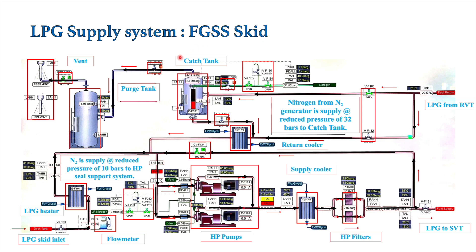Next, let's see why we have a catch tank in the FGSS skid. The catch tank comes into use when we are either starting or stopping the engine. During starting, this catch tank provides positive suction head to the HP pumps. The catch tank is always maintained at 23 bar, and this 23 bar pressure is maintained by nitrogen supply. Nitrogen is supplied at around 34 bar and reduced by a pressure control valve that always maintains the catch tank at 23 bar, providing positive suction head for the HP pumps.